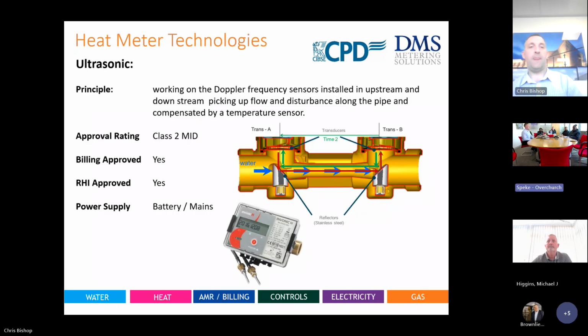So the 2 other measuring principles would be, in this case, ultrasonic. This is based on a tube, a tube body, that differs in different sizes, but the mentality is the same. Water passes through the tube. The tube has a circumference. It has something called a transit time signal. What happens is it bounces a signal through transducer A, which is on the left-hand side there, and then bounces that signal in relation to the velocity of the water. The higher the velocity of the water, the higher the flow rate.